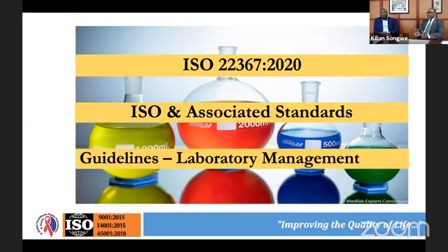But just as you close, you touched on two very important words in ISO 15189. And it's also very important when we're talking about ISO 22367, which looks at risk. That is the element of verification, ensuring that what the manufacturer said you're going to get is what you actually get in your systems. And the element of validation, which basically says if you're going to be acting out of the standard approved requirements, then you have to conduct validation. Those two words in medical laboratory practice are used very interchangeably so often. However, they mean very different things. And if they are not looked at carefully, that's a source of big error.